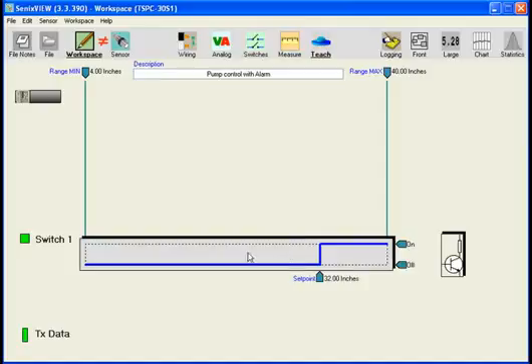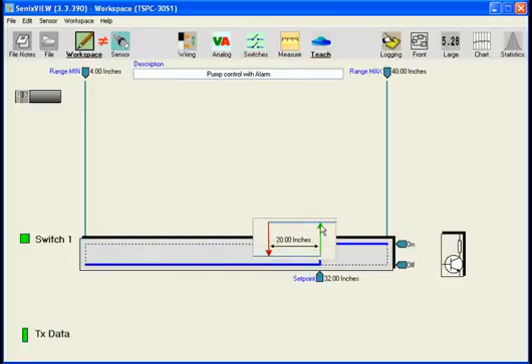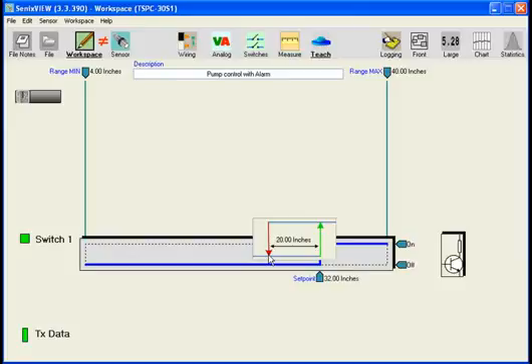Now the logic of what we have set up is the following. As the level, the sensor is here, remember? As the level drops, we reach the threshold and the pump turns on. And the level will rise. But it'll have to go a full 20 inches before it turns off.